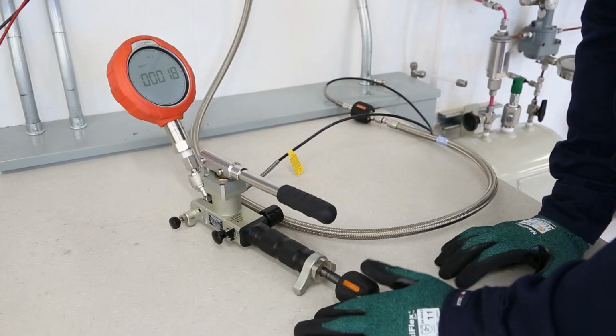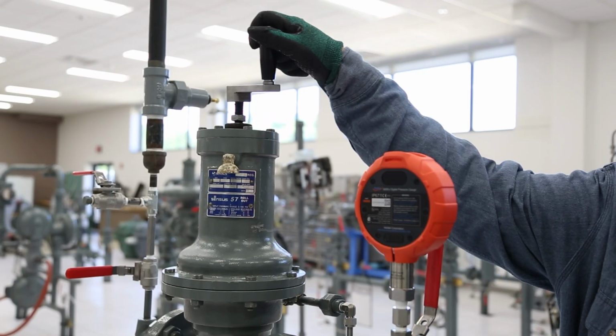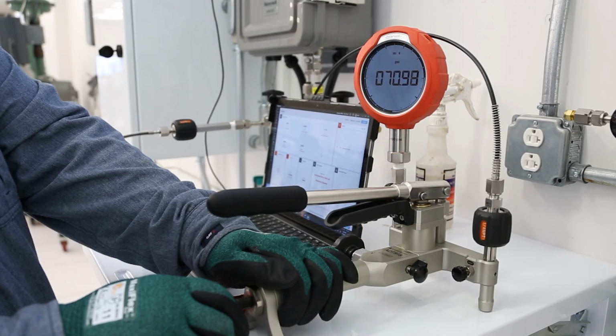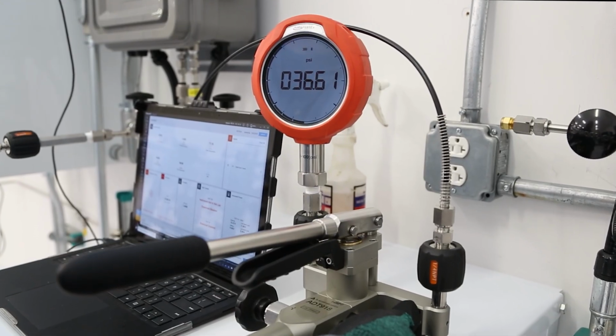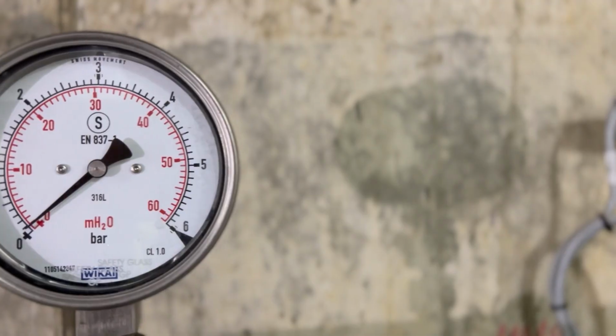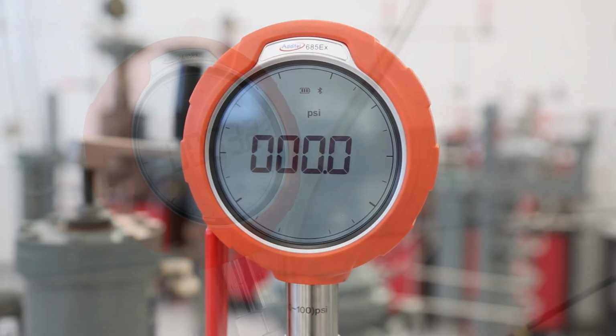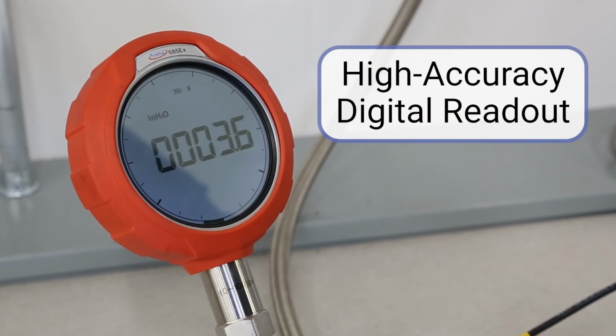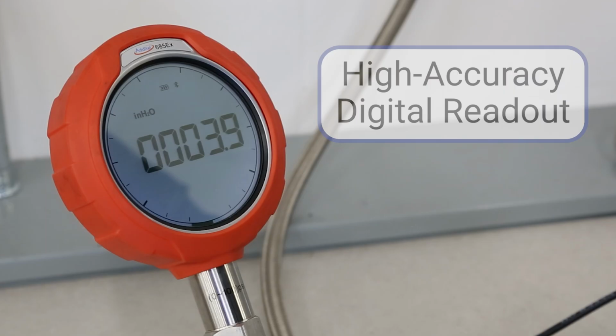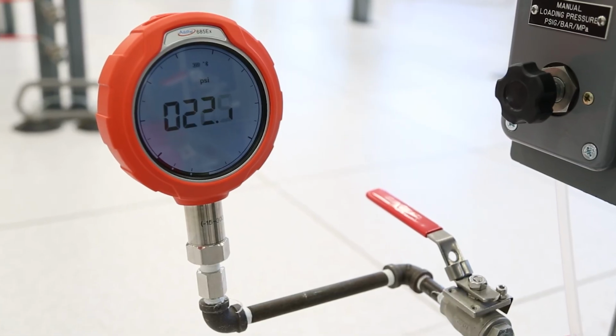Whether performing a pressure switch test, adjusting a regulator, or calibrating electronic pressure recorders, the 685Ex delivers lab-grade precision. By replacing analog gauges with a clear digital readout, technicians could be sure their measurements were accurate and reliable, even during low-pressure applications.